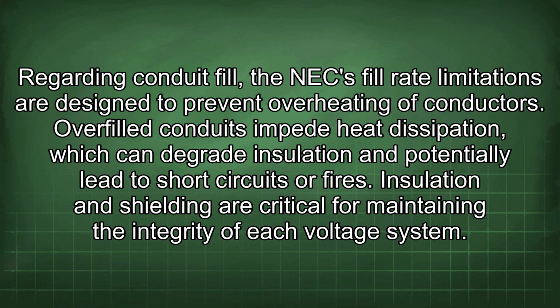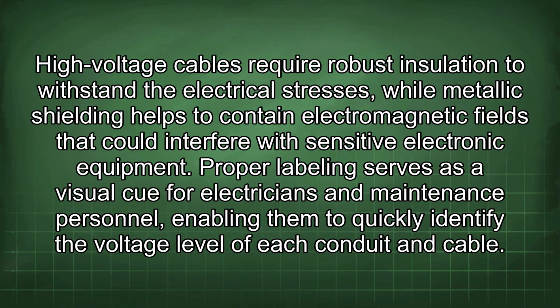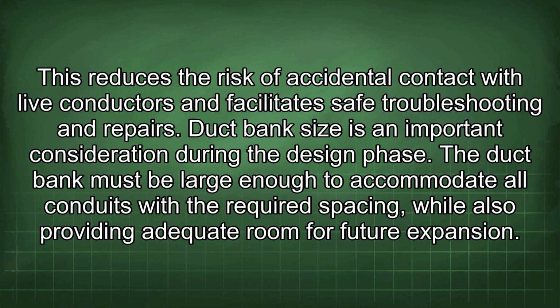Insulation and shielding are critical for maintaining the integrity of each voltage system. High voltage cables require robust insulation to withstand the electrical stresses, while metallic shielding helps to contain electromagnetic fields that could interfere with sensitive electronic equipment. Proper labeling serves as a visual cue for electricians and maintenance personnel, enabling them to quickly identify the voltage level of each conduit and cable. This reduces the risk of accidental contact with live conductors and facilitates safe troubleshooting and repairs.